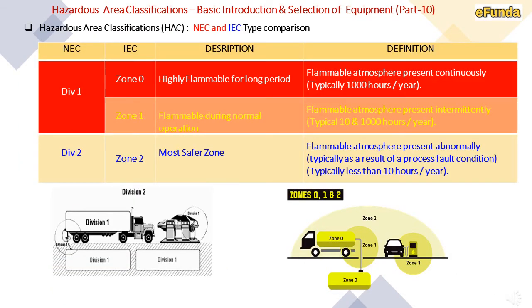NEC and IEC type comparison is covered in a table: NEC Division 1 is equivalent to IEC Zone 0 and Zone 1; NEC Division 2 is equivalent to IEC Zone 2. The descriptions and definitions remain the same. Figures are shown clearly indicating how the divisions and zones 0, 1 and 2 are classified.